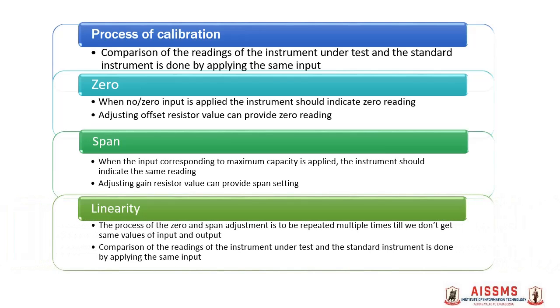When we apply the input corresponding to the maximum capacity of the instrument, it should indicate the same maximum value. If it is not showing the same reading, we need to adjust the gain resistor value to provide the span setting. This is the span adjustment. This process of zero and span adjustment is to be repeated multiple times — at least three times — until we get the same values of input and output.